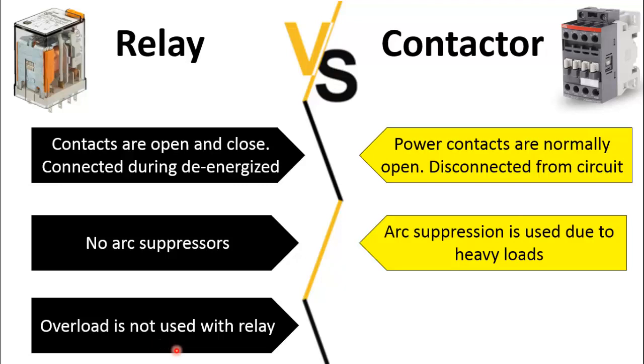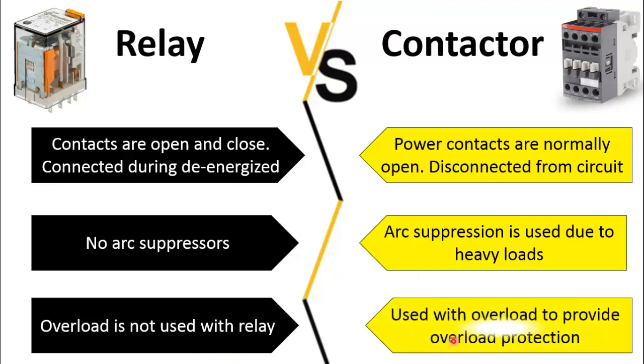The last difference is that an overload relay is not used with the relay, because relays are meant to switch loads that do not require a separate overload relay — the overload protection is done through a circuit breaker. Whereas since contactors are used mostly to switch electric motors, which require a separate overload relay, the overload relay must be installed with the contactor to provide overload protection for the motors.